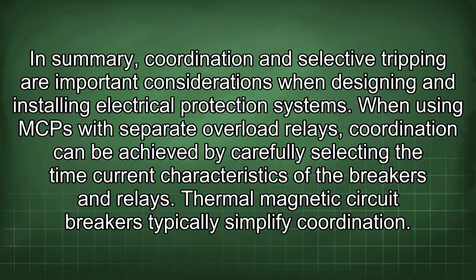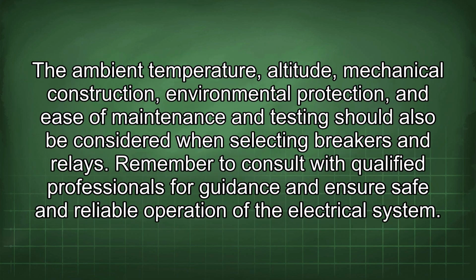In summary, coordination and selective tripping are important considerations when designing and installing electrical protection systems. When using MCP with separate overload relays, coordination can be achieved by carefully selecting the time current characteristics of the breakers and relays. Thermal-magnetic circuit breakers typically simplify coordination. The ambient temperature, altitude, mechanical construction, environmental protection, and ease of maintenance and testing should also be considered when selecting breakers and relays. Remember to consult with qualified professionals for guidance and ensure safe and reliable operation of the electrical system.